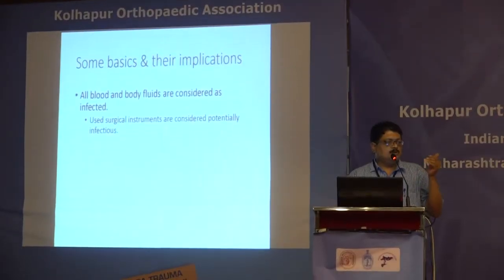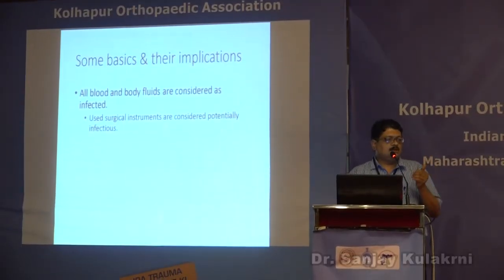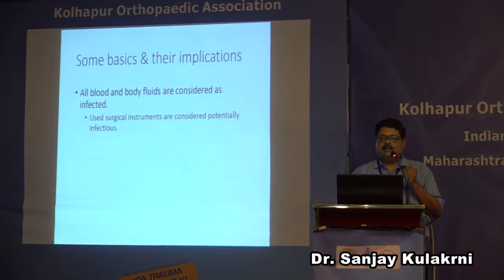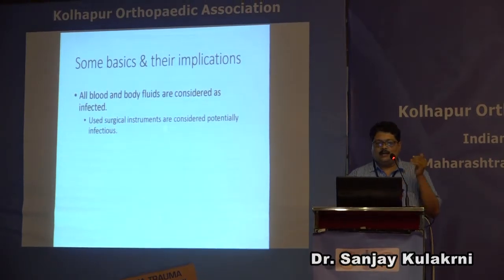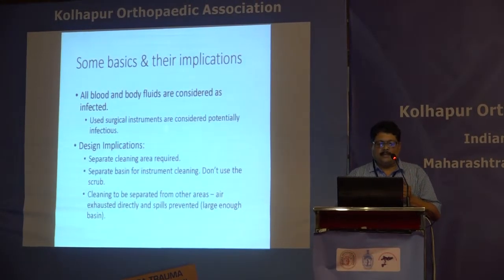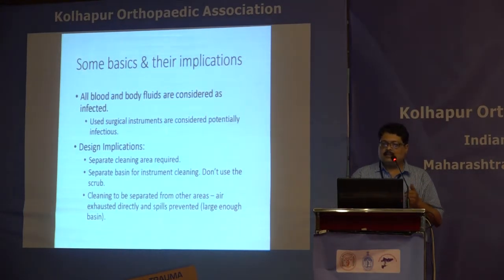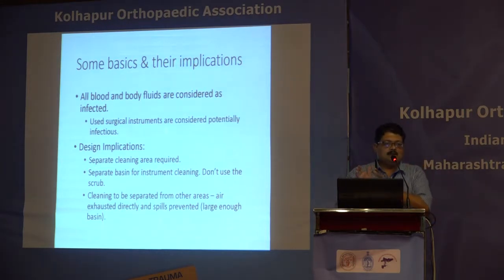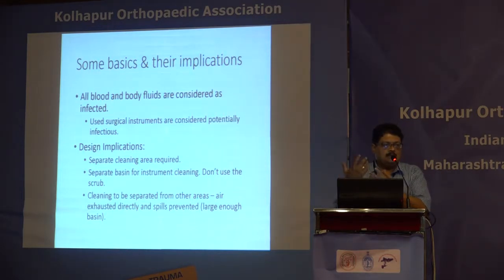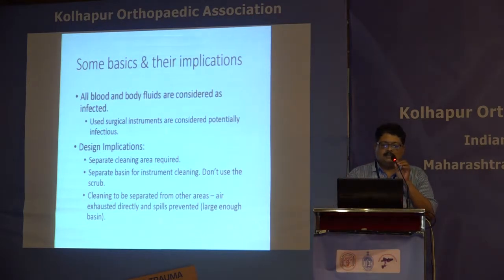By this protocol, used surgical instruments are considered as potentially infected, so they have to be handled in a particular manner. This has implications for design in that a separate cleaning area is required in the CSSD. Instruments should not be washed in the scrub basin, because the scrub basins will get contaminated — in case there's an infection, when you are scrubbing it will come on your hands.